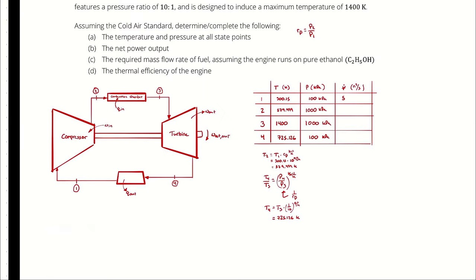Having a maximum temperature is often a design criterion of a gas turbine engine. You typically want as much power or efficiency as possible from a given size, and that comes from having higher maximum temperatures. The limiting factor for many gas turbine engines is the design and material of the turbine blades. Depending on design and cost, you might tolerate a higher maximum temperature, but regardless, the maximum temperature is something you design around.